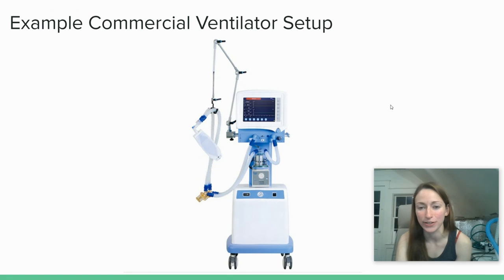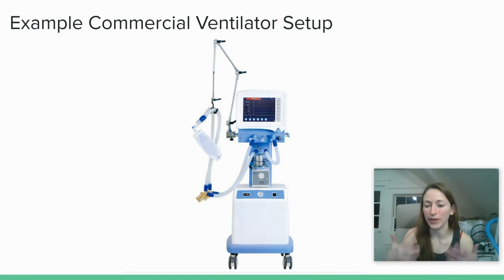So here's a random commercial ventilator that I found on the internet. And I assume that there are some flow controllers existing within the body of this device. And if I look at the respiratory circuit, I can see that this is the inspiratory side coming out of the device that moves into a heated humidification chamber. Okay, so that's a heated humidifier. And from there, we move out into some water traps. Here is a test lung or a breathing bag that's taking the place of the patient lungs at this time. And then the expiratory circuit moves back into the device where there are sensors and additional valves and things to control the flow. So it's good to look at existing commercial devices to see what you might be missing.